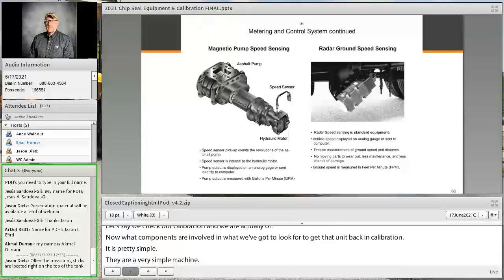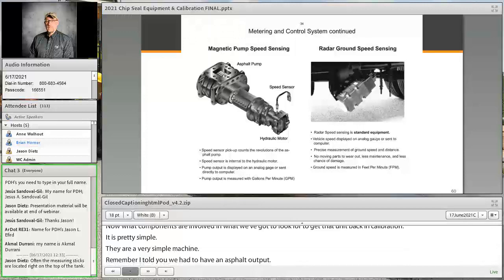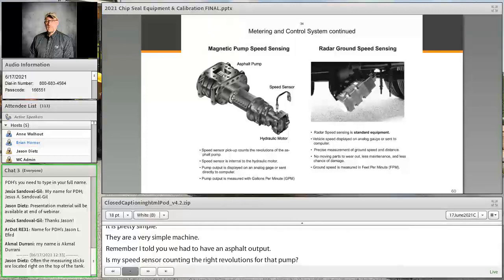We're not going to get into all the detail here, but that speed sensor is looking at a gear in that motor to tell us how fast that pump's turning. There's settings in the computer, and over the years we've used different speed sensors that we got to look at. The tolerance between the gear and the sensor makes a difference, but it's one area to look at. If we're not in calibration, we need to check to make sure we're counting the correct number of revolutions of our pump.